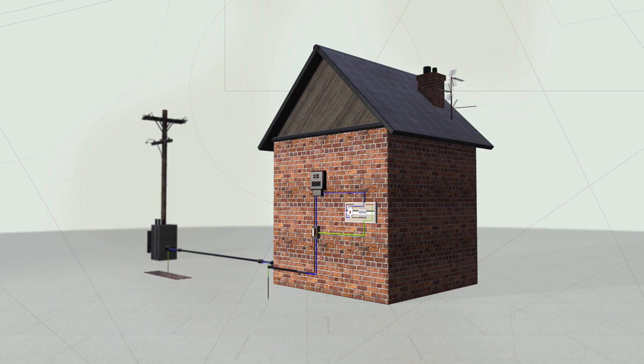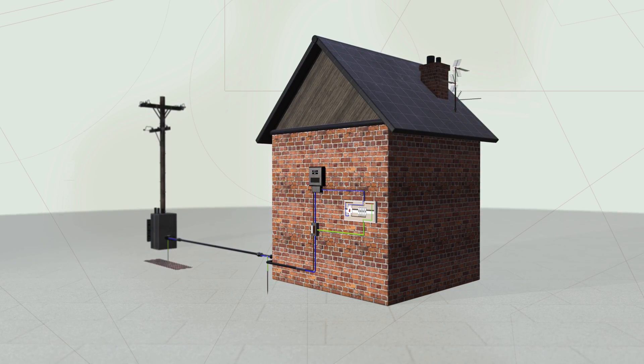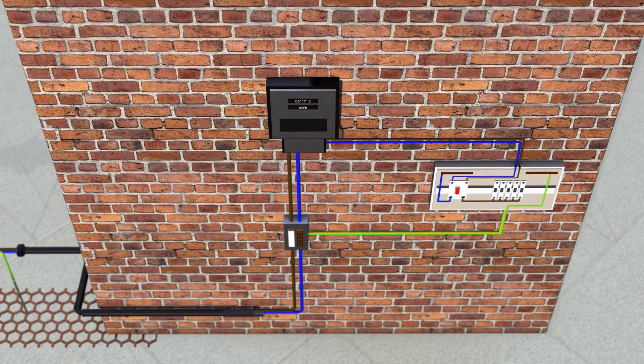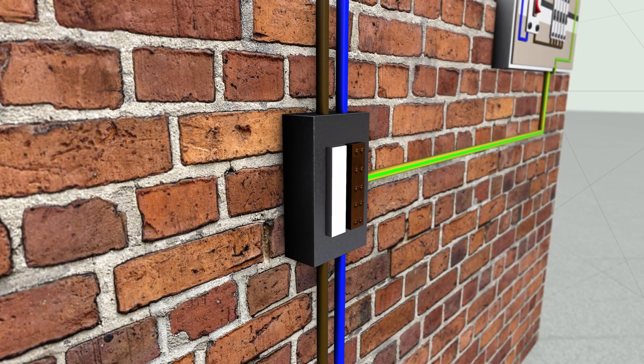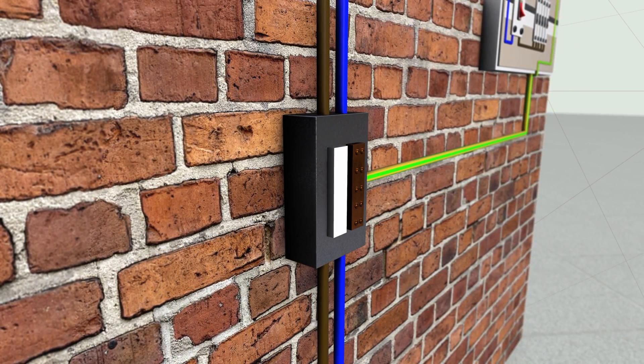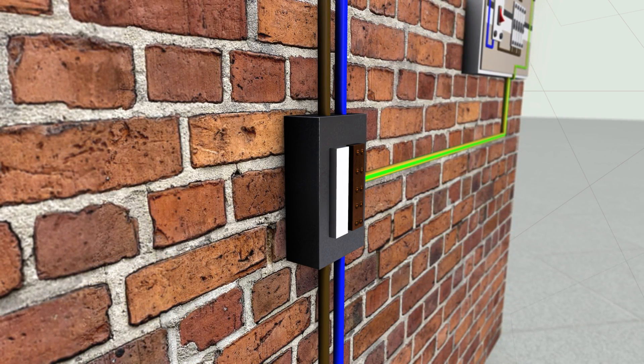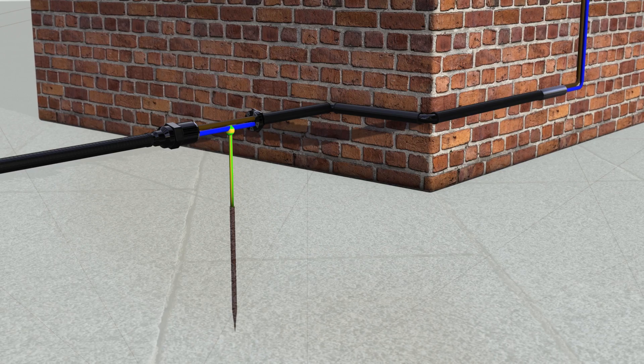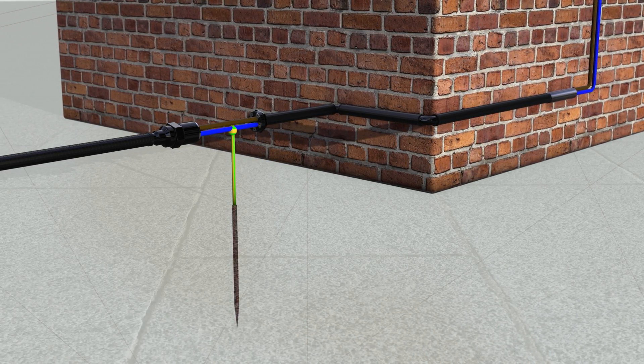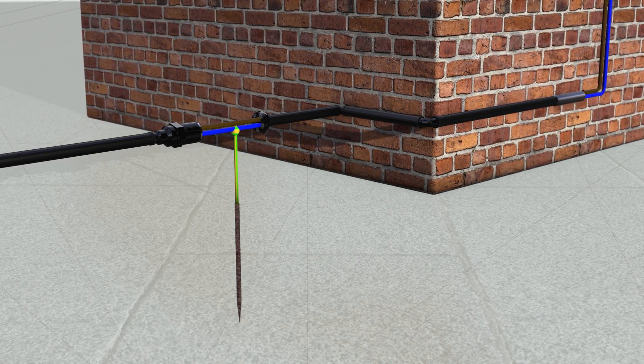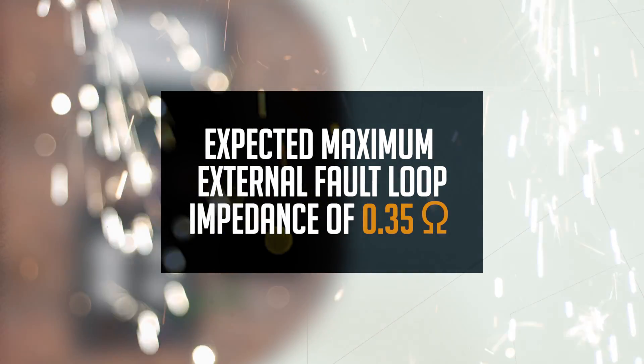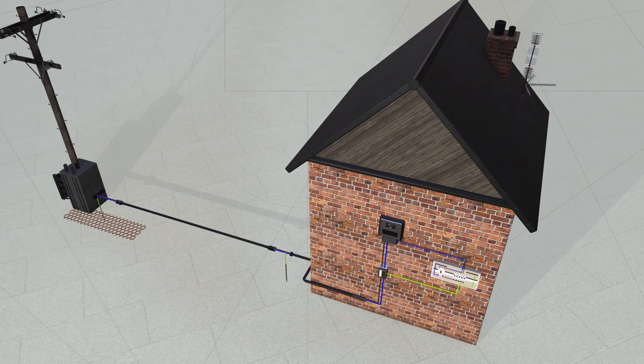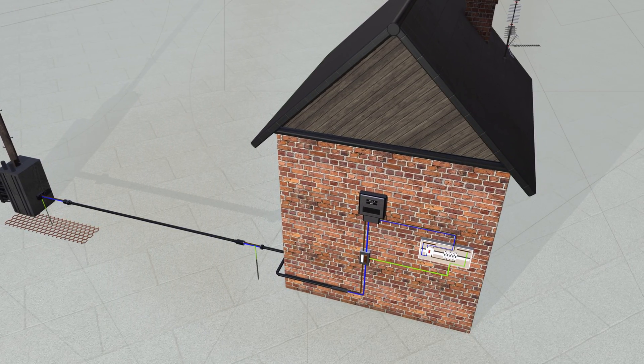In a TNCS arrangement, the earth and neutral are combined in the same conductor from the distribution transformer up to the consumer's installation. As the supply neutral is also used as the earth conductor, it is called a PEN conductor — protective earth and neutral. Once the electrical supply is terminated into the service head, the PEN conductor is split into two terminals: one neutral and one earth. This is the most common earthing arrangement in the UK, also called PME — protective multiple earth — because it could have more than one source of earth electrode along the length of the buried supply cable in the street. The DNO will declare an expected maximum external earth fault loop impedance of 0.35 ohms. This system may be identified by looking at the DNO service head — if the earth conductor comes from inside the service head, it is likely to be PME.